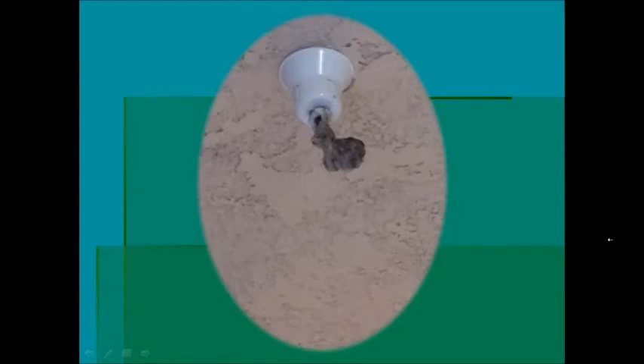I went to the very last head on the line under the protected canopy, and sure enough, the wasps built the little housing development that you see there right on the tip of the fire sprinkler head. So what's the problem there? Most of you on the call absolutely know what the magic number is, right? 18 inches. We need 18 inches of clearance below these sprinkler heads for them to operate.